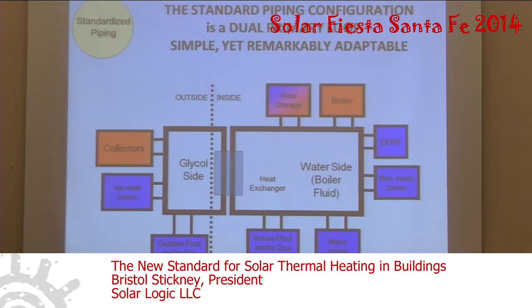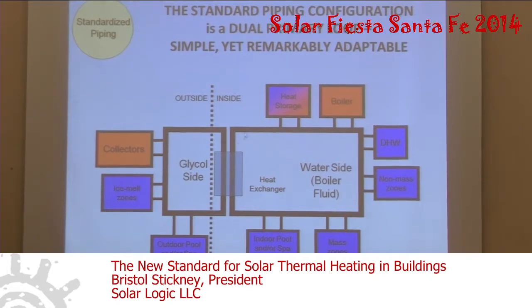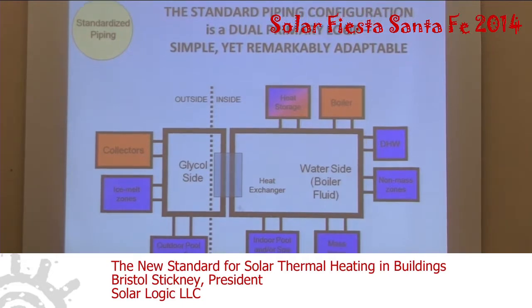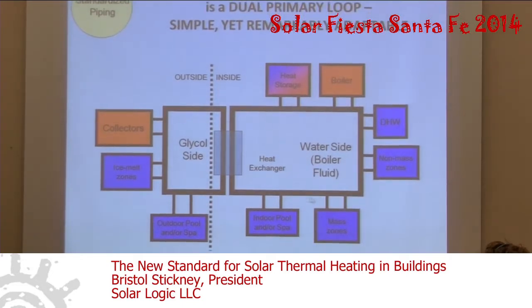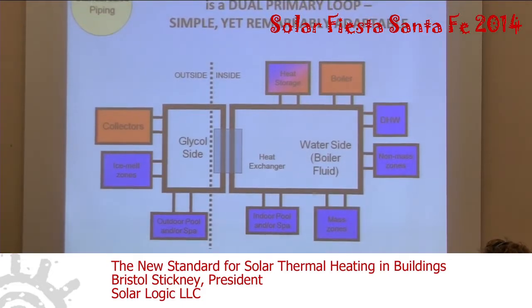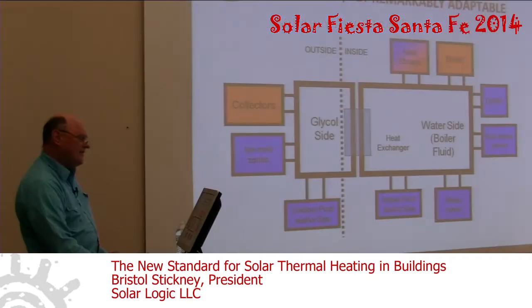Here's how we do the plumbing. The new standard in plumbing is making good use of what is known in the plumbing industry as the primary loop. Here is a primary loop that hangs in your boiler room next to your boiler. This thick black line here, you can imagine that it's made out of copper tubing and it has water flowing around in it, and that's the boiler water.